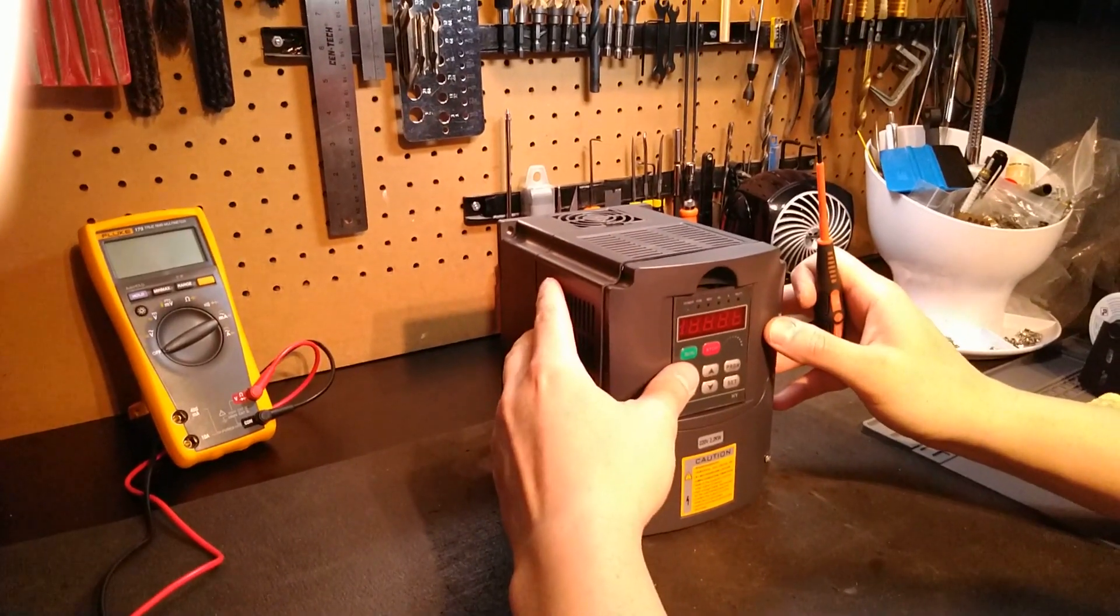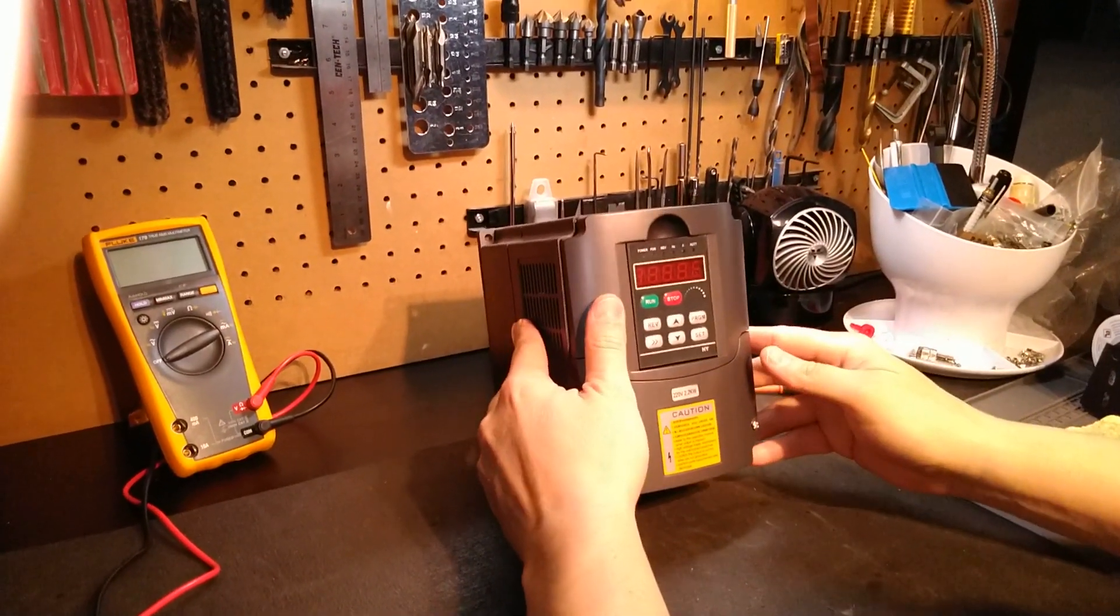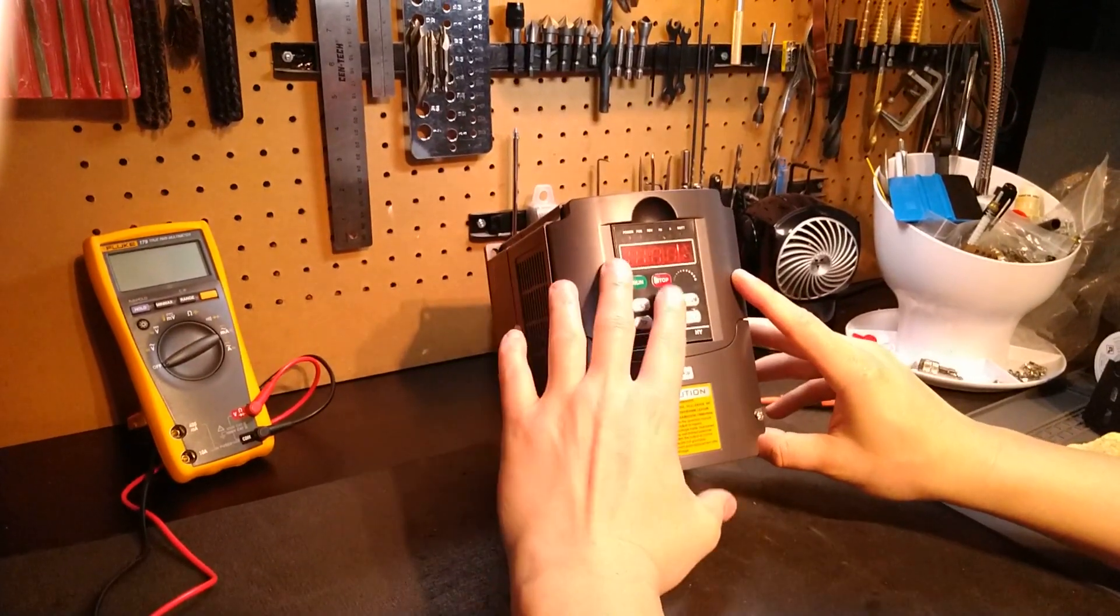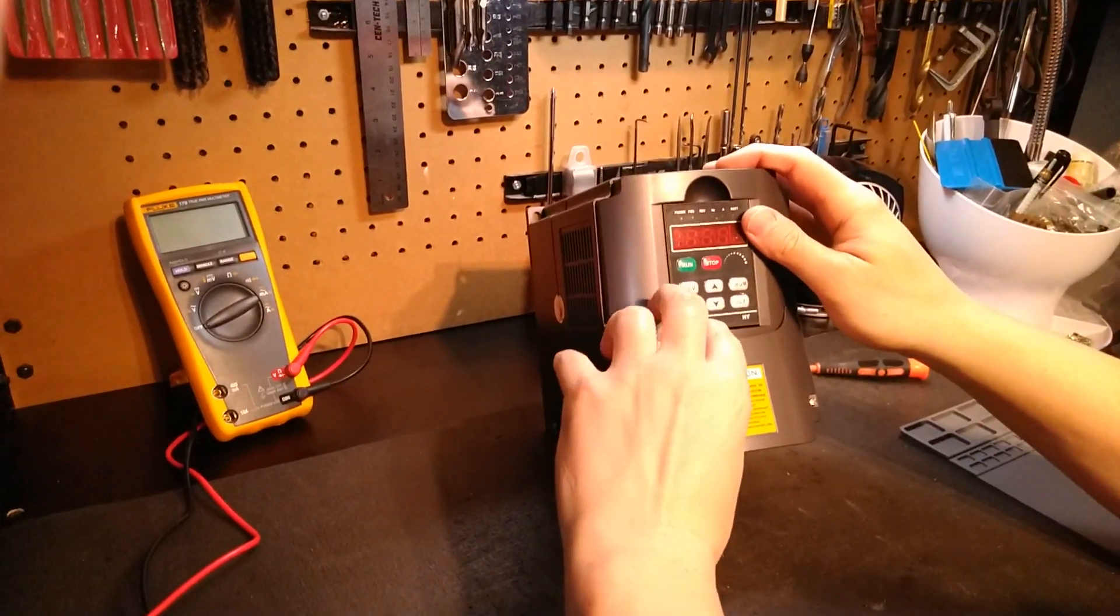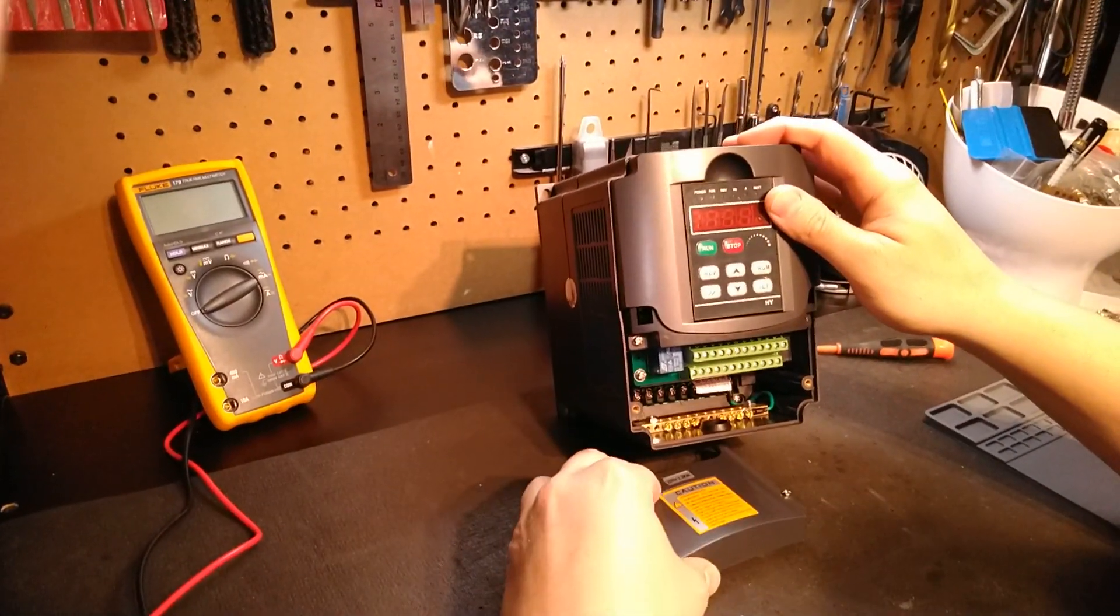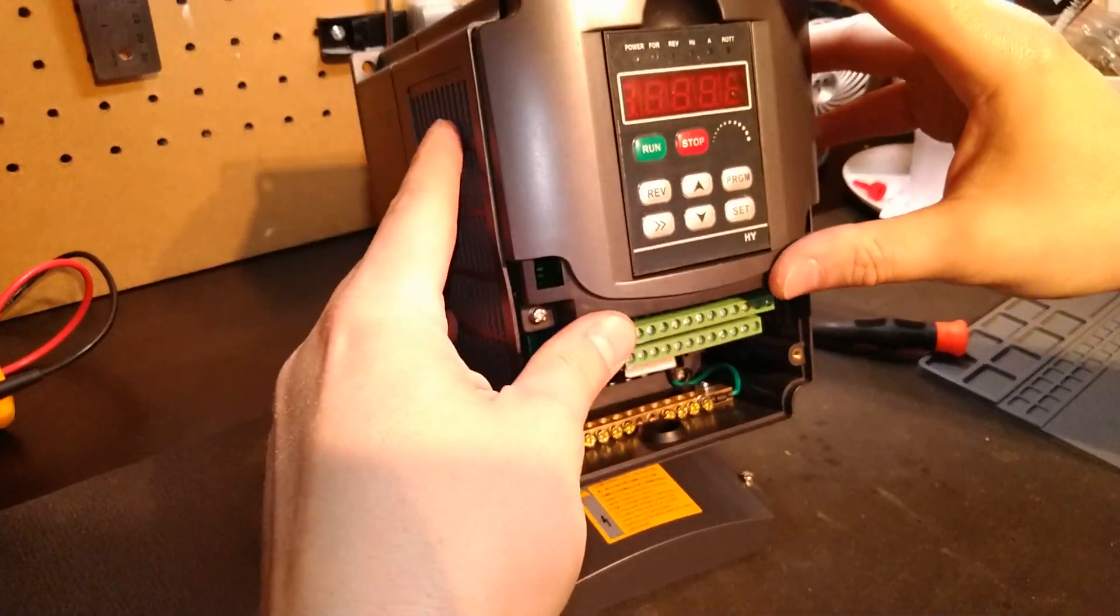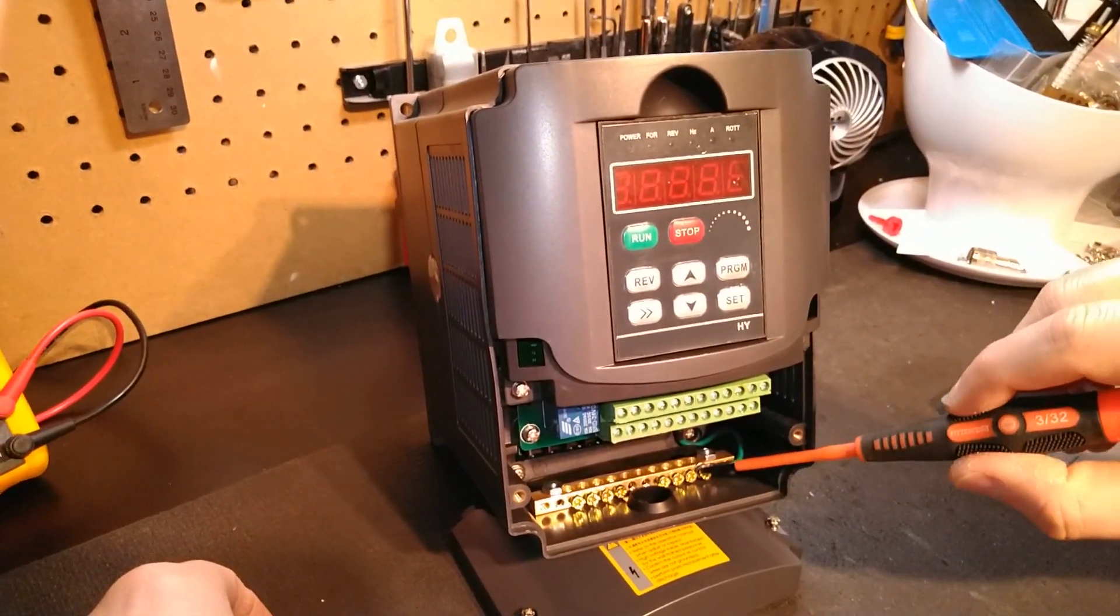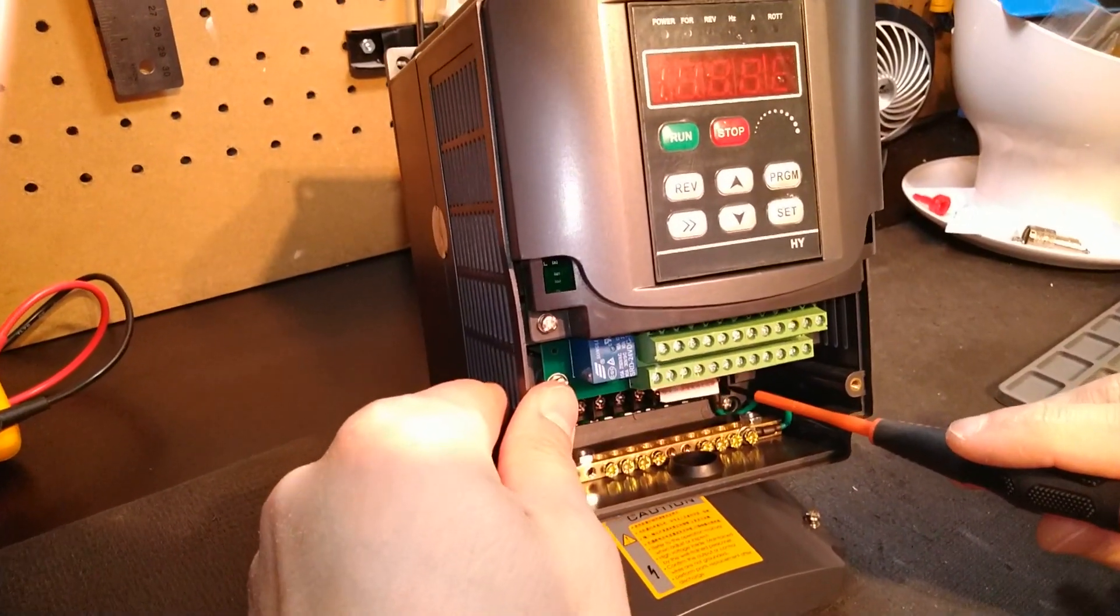Best practice with this is done very simply. You can see we've got a HYVFD here, nothing new. Many of you are familiar with this VFD. It looks totally stock on the front. However, when we go inside the unit, you can see she's been modified. And when I say modified, you can see that ground bus bar bolted in, and we actually have a terminal split right here.